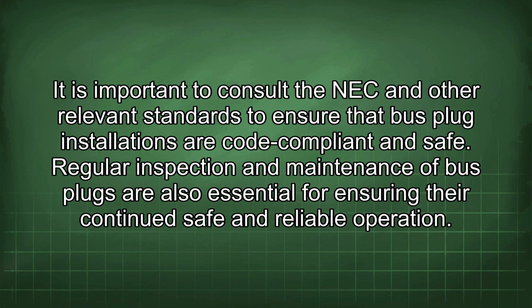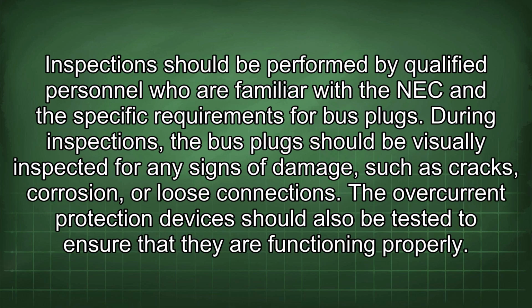and safe. Regular inspection and maintenance of bus plugs are also essential for ensuring their continued safe and reliable operation. Inspections should be performed by qualified personnel who are familiar with the NEC and the specific requirements for bus plugs. During inspections, the bus plugs should be visually inspected for any signs of damage, such as cracks, corrosion, or loose connections. The overcurrent protection devices should also be tested to ensure that they are functioning properly.